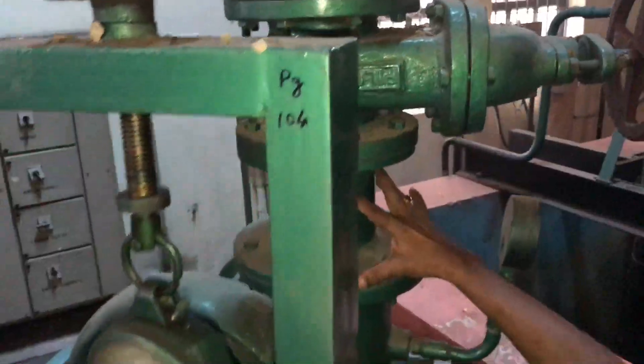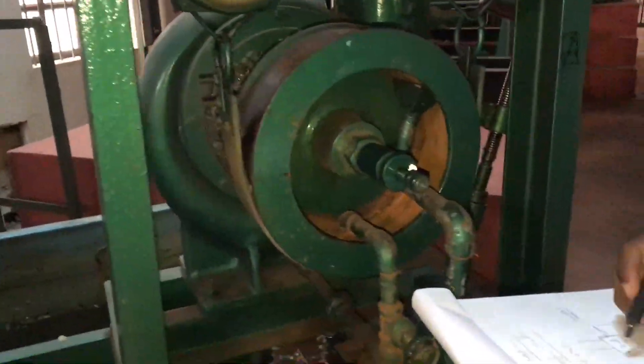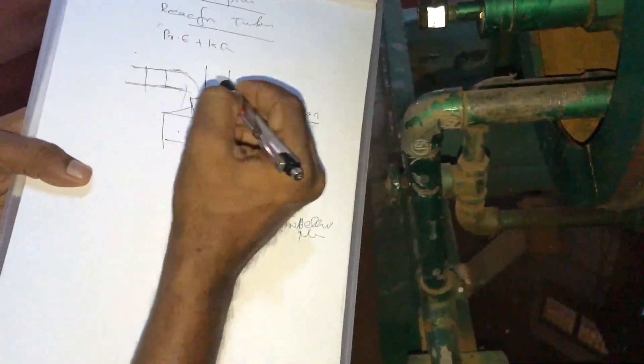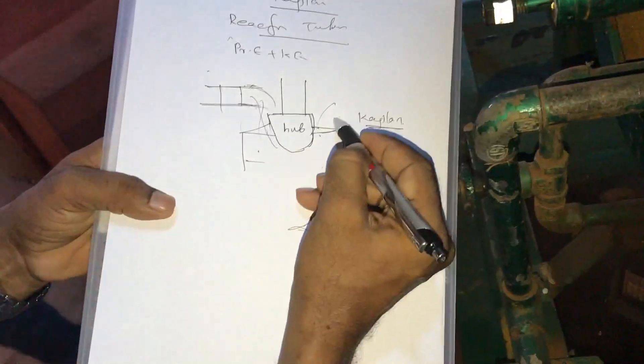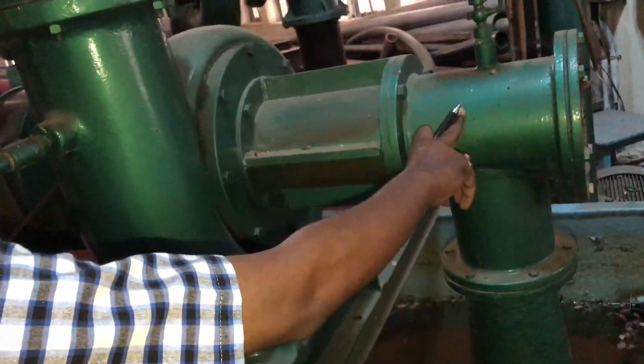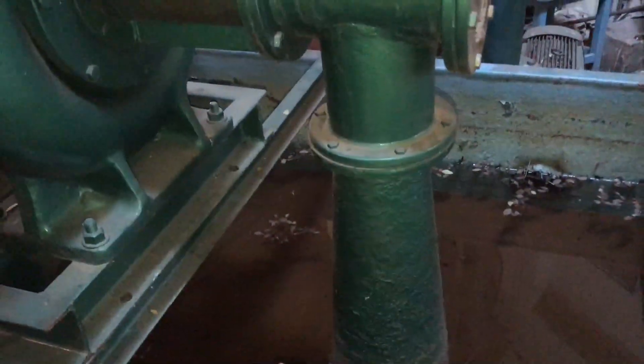This is the inlet of the turbine. Water available at this end has both pressure energy and kinetic energy. When the fluid passes through the stay vane, gate blade, and then the runner blade, the pressure energy goes on decreasing and is converted into kinetic energy. At the exit of the turbine the pressure is less than atmospheric. To discharge the fluid from the turbine exit to the tail race, a diverging pipe called the draft tube — specifically a conical draft tube — is used.